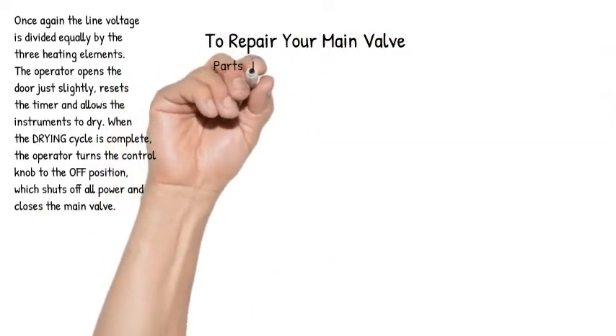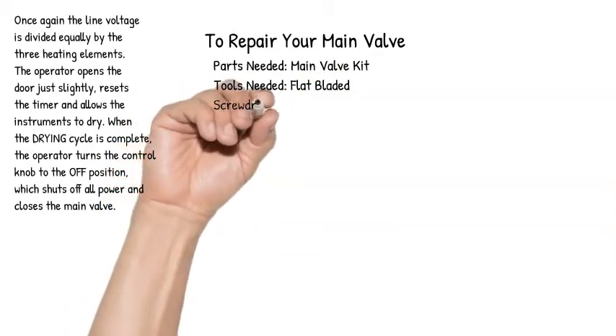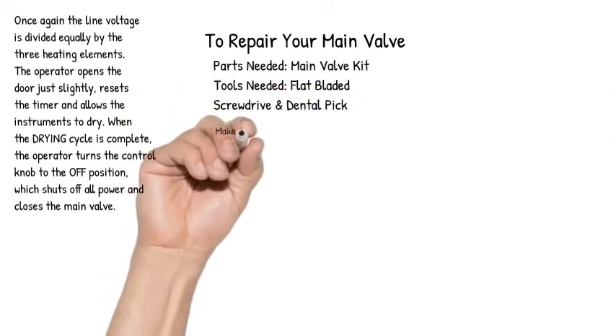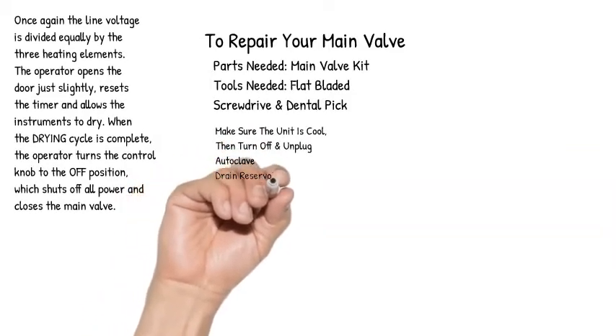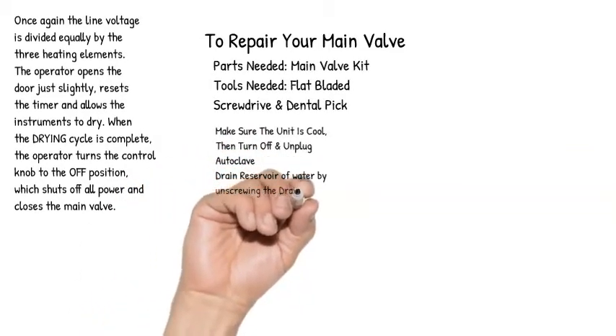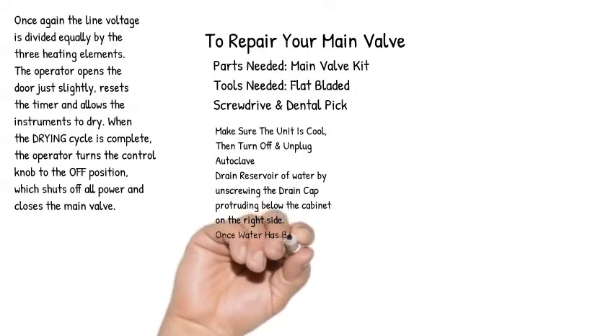To Repair Your Main Valve. Parts needed: main valve kit. Tools needed: flat bladed screwdriver and dental pick. Make sure the unit is cool, then turn off and unplug autoclave. Drain reservoir of water by unscrewing the drain cap protruding below the cabinet on the right side.